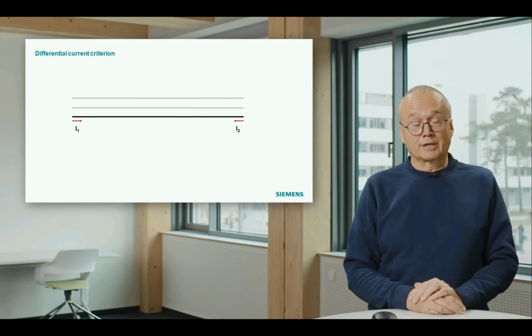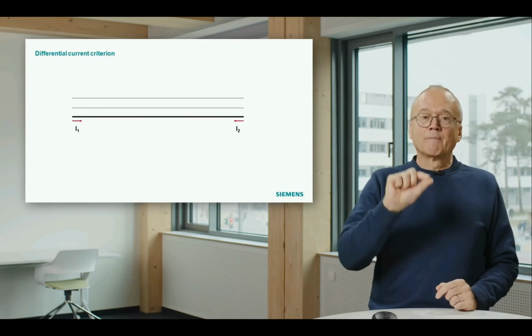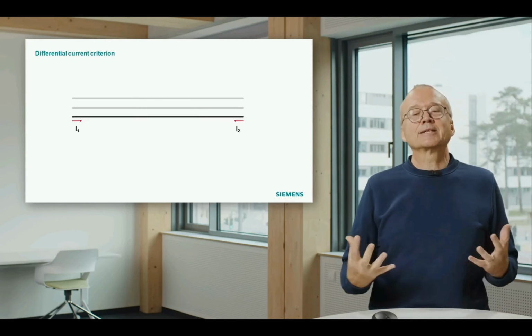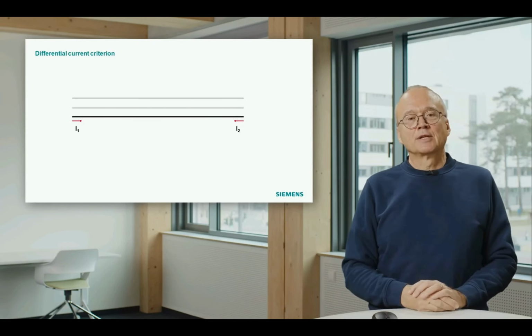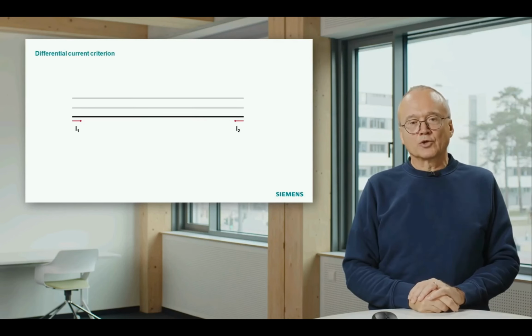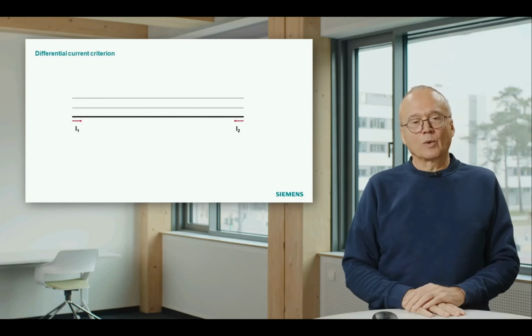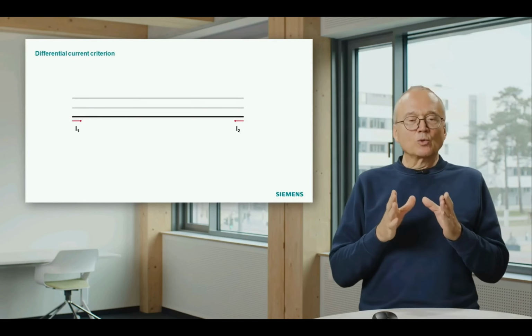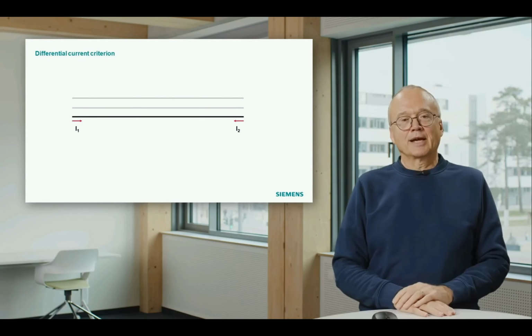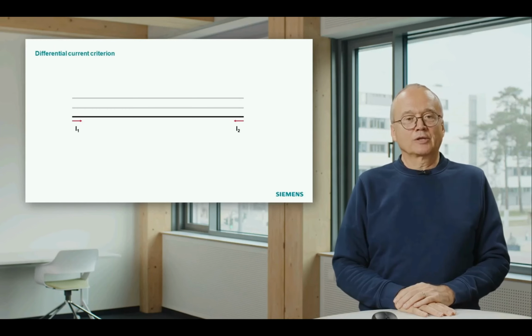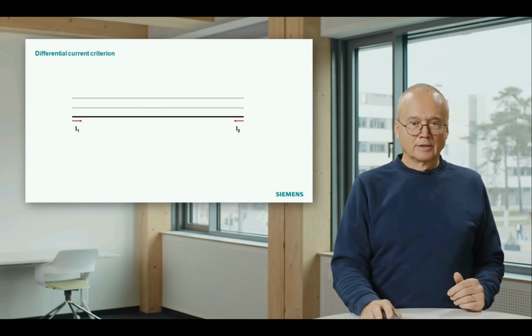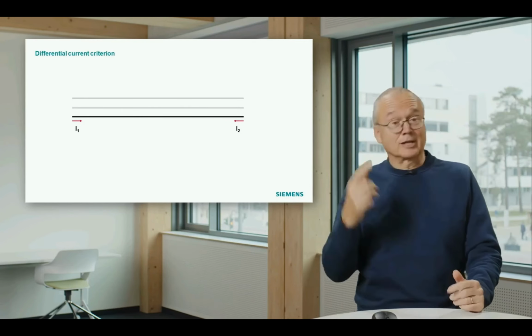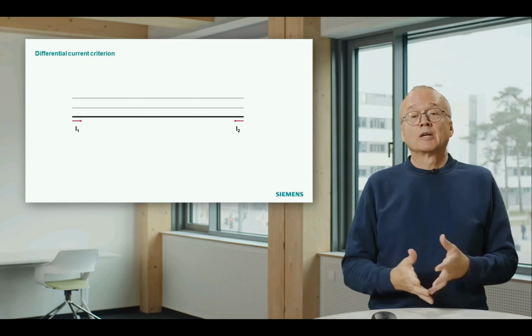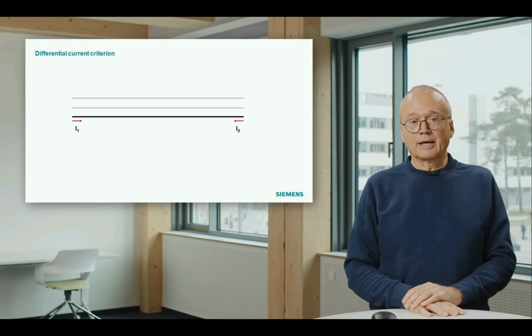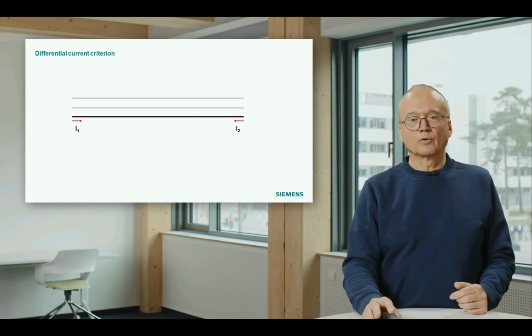If we now have a short circuit on this phase, that means a connection from the phase to ground or from this phase to another phase, it disturbs our equation. And that means the sum of the two currents is no longer equal to 0 because part of the current flows another way. That means we can use the sum of the measured currents as a good indication, is there a short circuit on the device or not. And that is the differential criterion. In this case, I introduced it just for a single line with two measurements. You can also use it for a multi-terminal line because the principle remains the same.